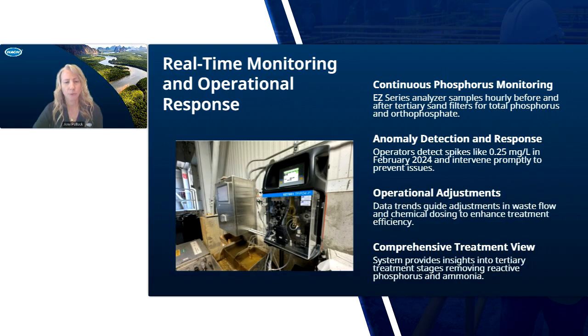Here's a photograph of the actual installation of the EZ Series 2-stream phosphorus analyzer installed in the final effluent UV building. It plays a critical role in real-time monitoring of the phosphorus levels. It samples hourly from pre and post sand filters, analyzing for both total phosphorus and orthophosphate. This dual-stream capability allows operators to detect anomalies and respond promptly.